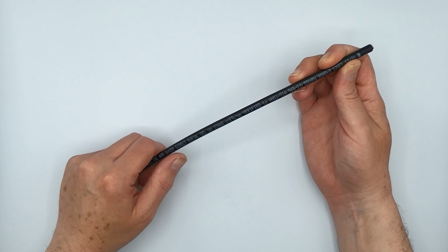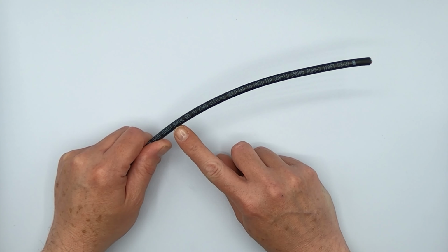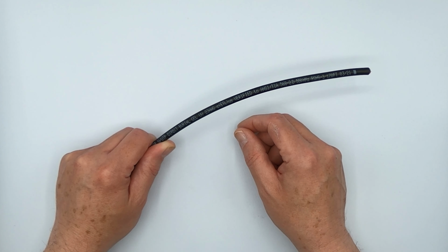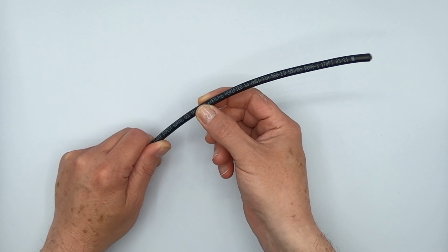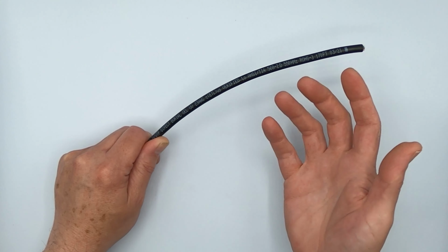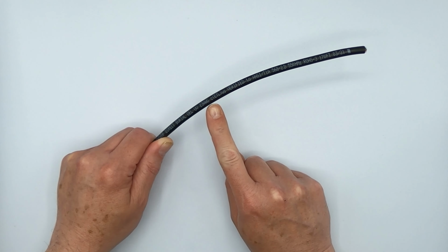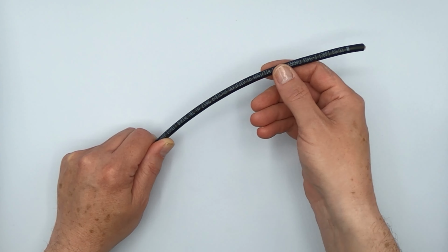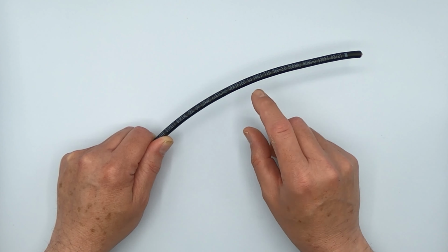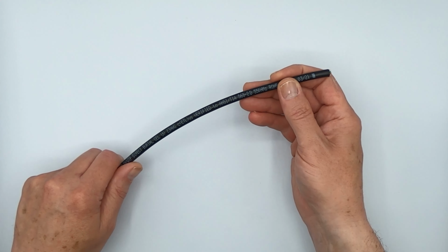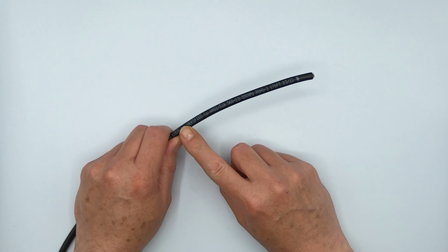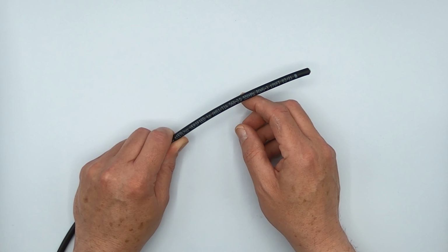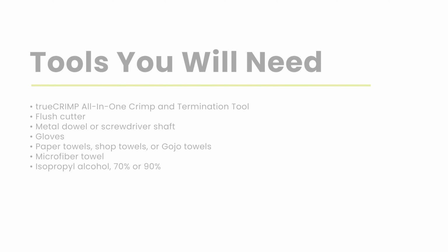This time I'm going to be talking about our Category 6 gel fill direct burial cable. Essentially, this is our Category 6 unshielded riser, but it's got a tough direct burial and outdoor UV protectant jacket, and it's got some petroleum based, that being paraffin wax and mineral oil, gel filling. It's not toxic, it's not flammable, but it does require a few extra steps to clean off the conductors and also some advice about how to get the stuff off your hands. So I say we go ahead and terminate the stuff and we'll show you the procedure.